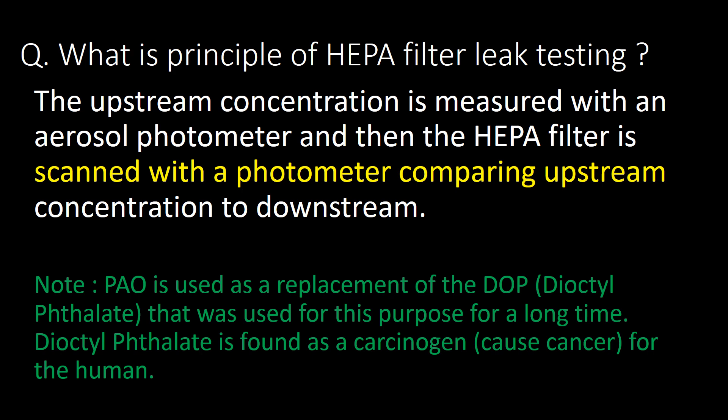What is the principle of HEPA filter leak testing? The upstream concentration is measured with an aerosol photometer, and then the HEPA filter is scanned with a photometer comparing upstream concentration to downstream. Note: poly-alpha olefin (PAO) is used as a replacement for the DOP test (dioctyl phthalate test) that was used for this purpose for a long time, as dioctyl phthalate was found to be a carcinogen causing cancer in humans.